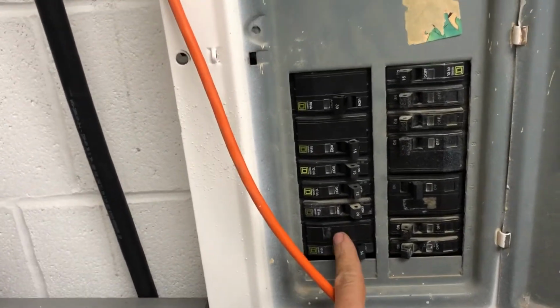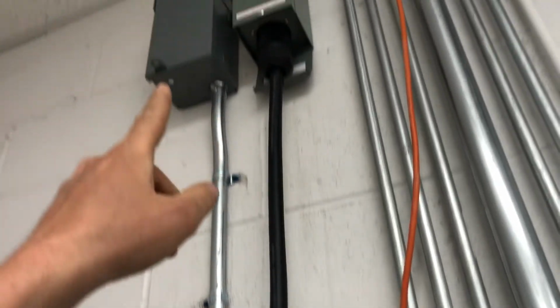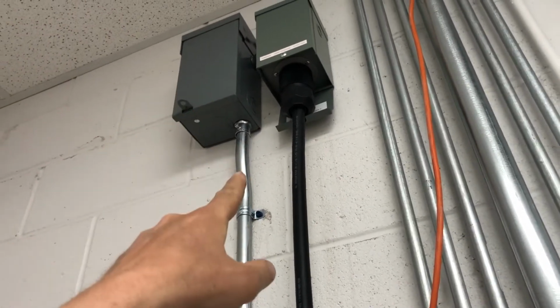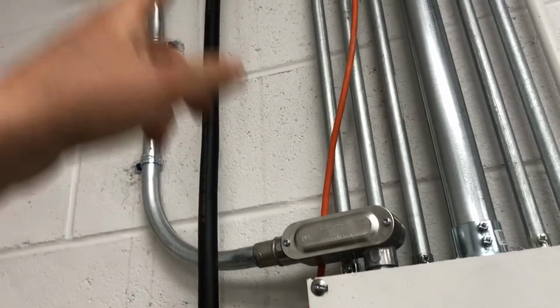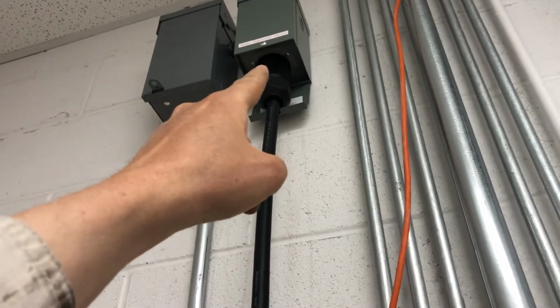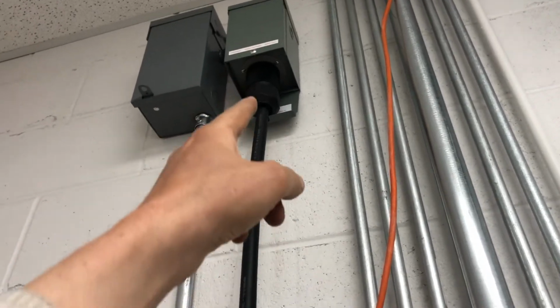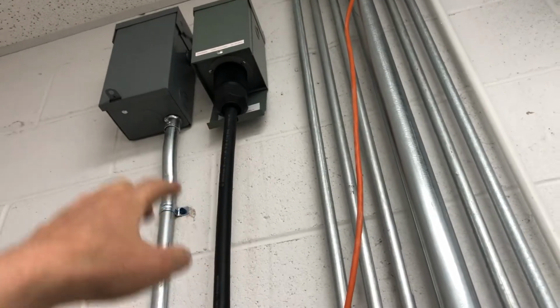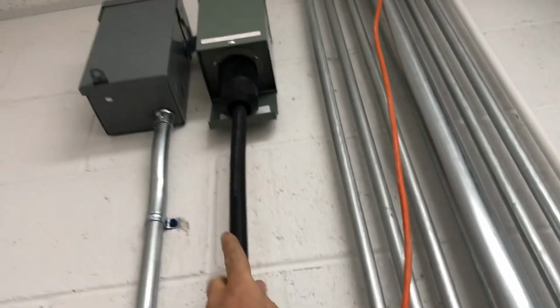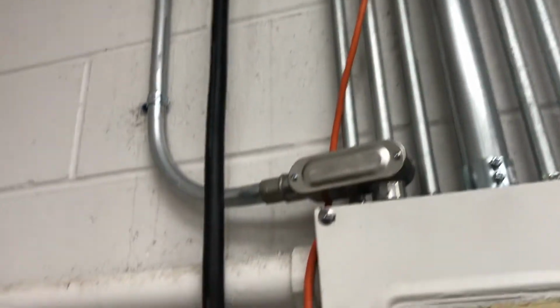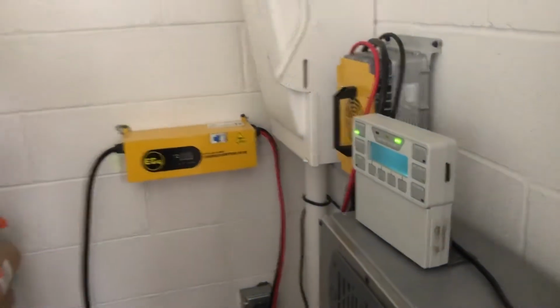So you can shut it off here, but if you're shutting it off permanently, I would lock out, tag out on that disconnect, because there is a sequence of opening doors and flipping switches where you could energize the live male terminals of that flanged inlet, which would become dangerous. And that's why it's also out of reach. It's up in the air where you can't get to it without a ladder. So the likelihood of accidental exposure is low. And that's the installation. Like I said, it's been running for about 3 months, and I really like it.